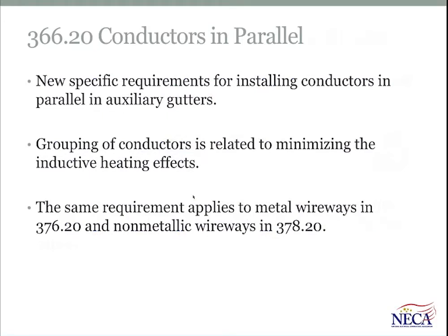And the last one we're going to cover, and then we'll open it up to some questions, is Section 366.20. It deals with conductors that are installed in parallel in wireways, in this particular case, auxiliary gutters. New requirements for installing conductors in parallel exist when they're installed in those arrangements in auxiliary gutters and in nonmetallic and metallic wireways. The change requires grouping of the conductors. So in other words, no longer can you just take a wireway or a gutter and just dump all the conductors of a parallel feeder or parallel branch circuit and install them in there without regard for the proximity of the conductors of the other groups.